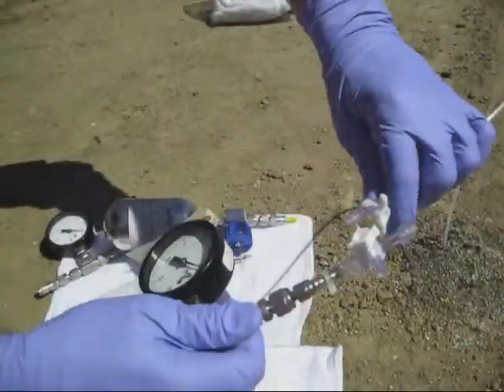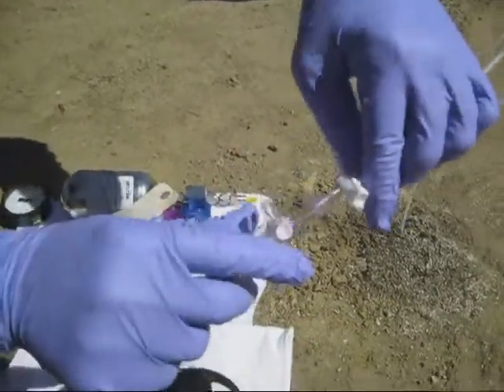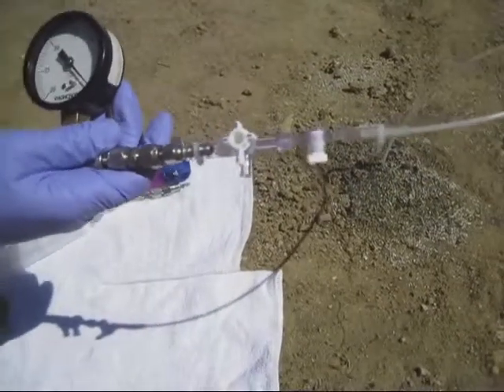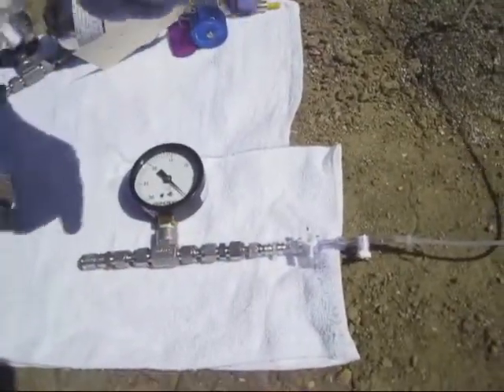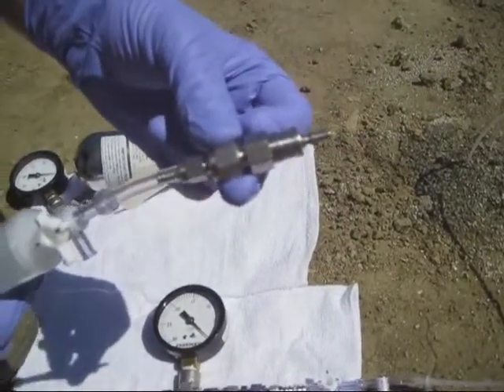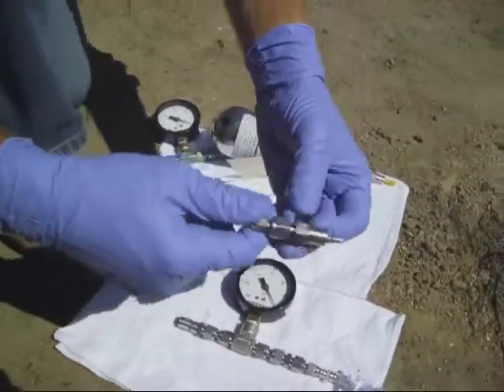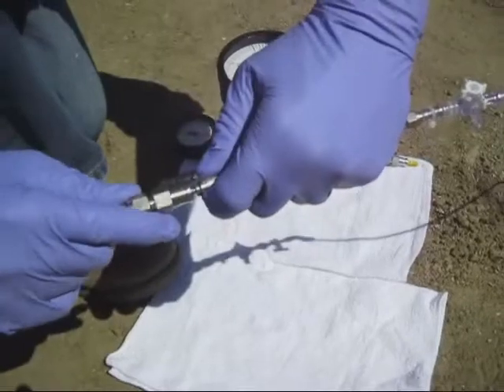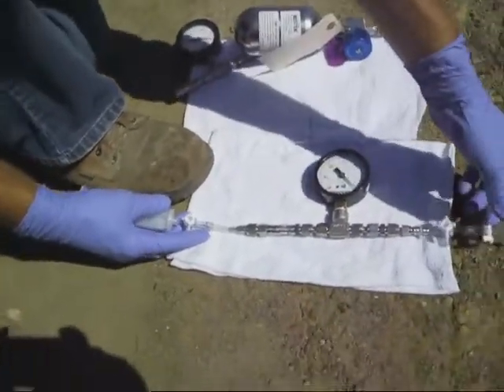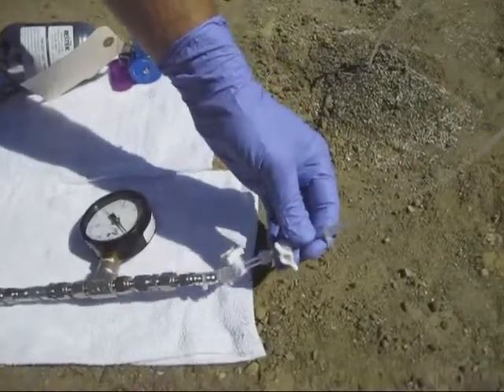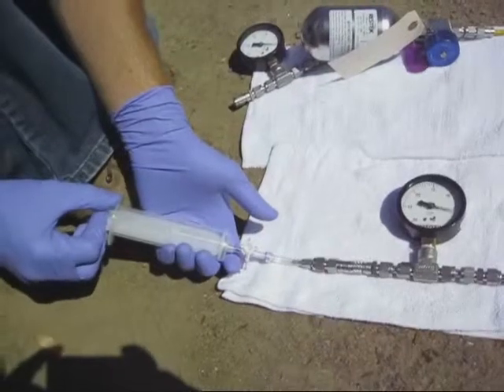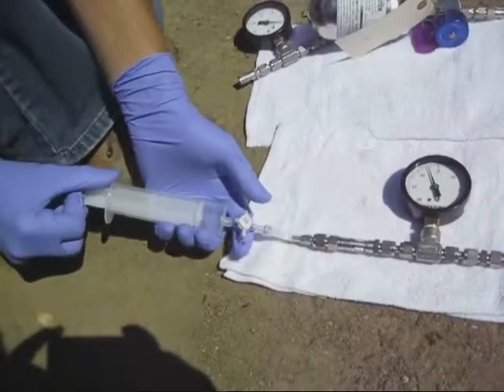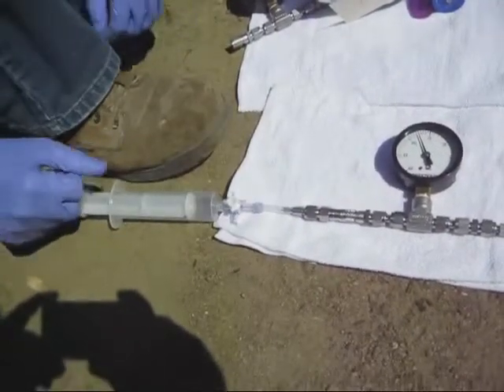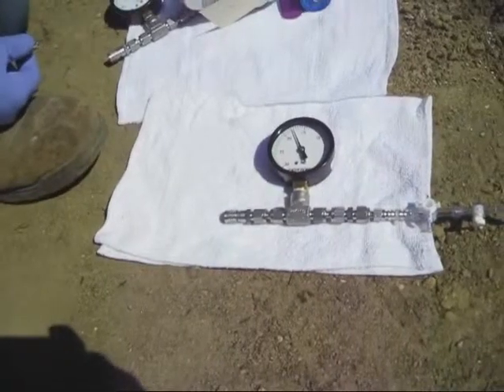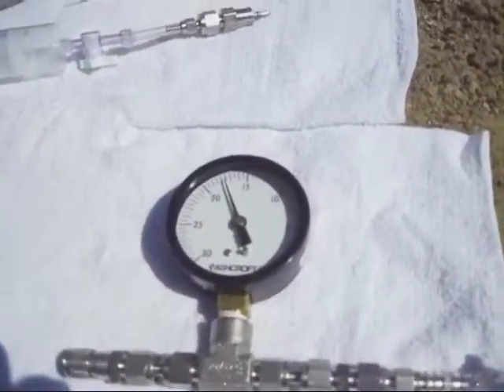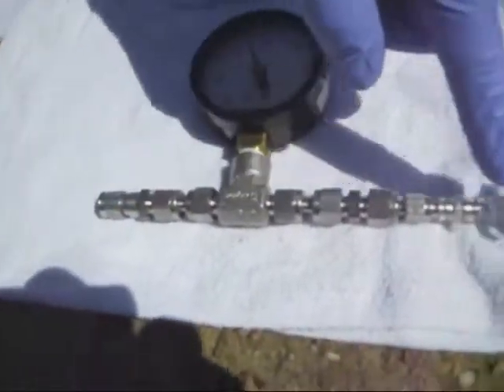In order to do that, we connect our assembly to our vapor probe using these Luer lock connections. Twist it on, make sure it's nice and tight. And using the male Swagelok adapter piece connected to a syringe, I'm going to connect to the female quick connect piece on the assembly. Now, making sure that the valve on the probe is in the off position, I'm going to draw back on my syringe, creating a vacuum, and then I'll quickly shut my valve off on my syringe, and I can disconnect my quick connect fitting.